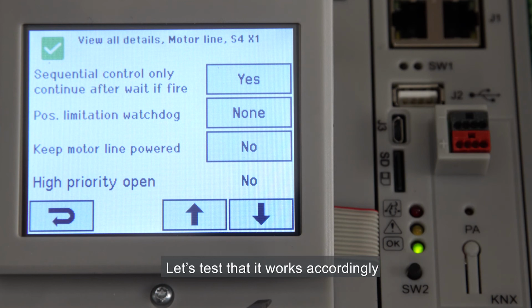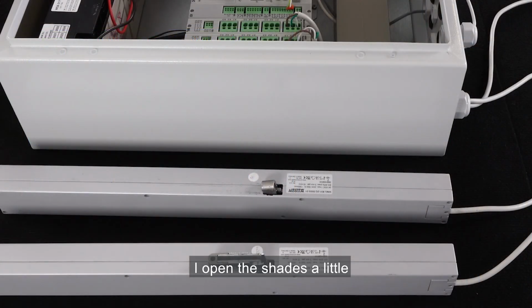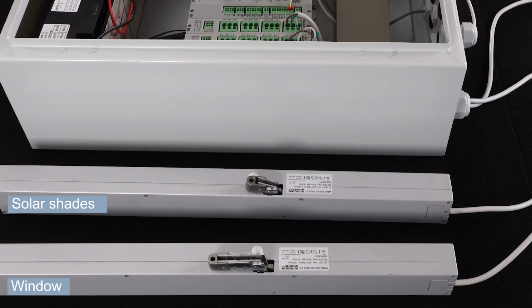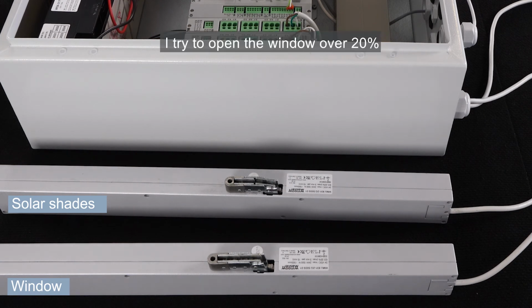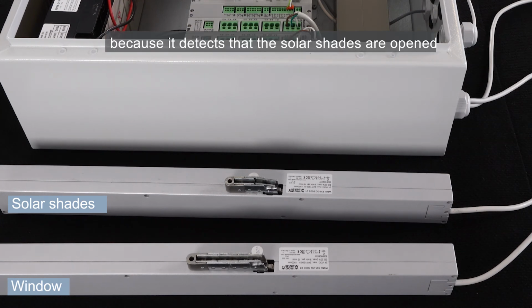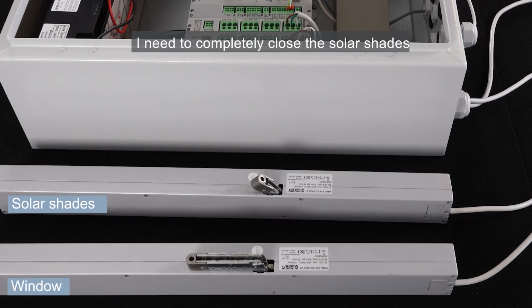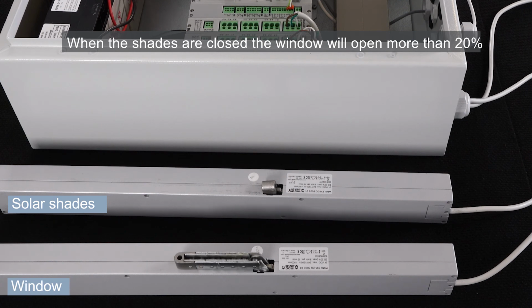Let's test that it works accordingly. I open the shades a little. I try to open the window over 20%, but it stops just before because it detects that the solar shades are opened. In order to be able to open the window more than 20%, I need to completely close the solar shades. When the shades are closed, the window will open to more than 20%.